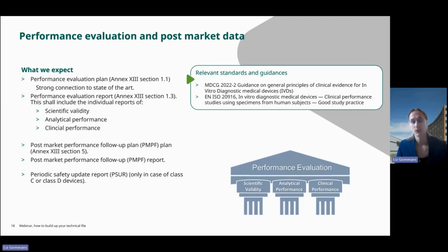So we would like to see the PSUR either for class D devices 1 year after the device has been certified, or for class C devices, we want to see it when we do a surveillance review, for example. So the device group, probably you've done sampling, so the device group is on the market already for over 1 year.